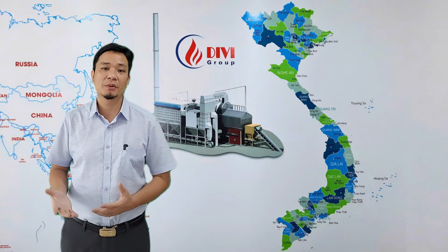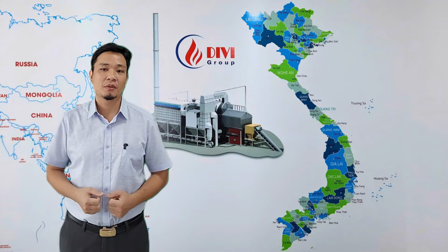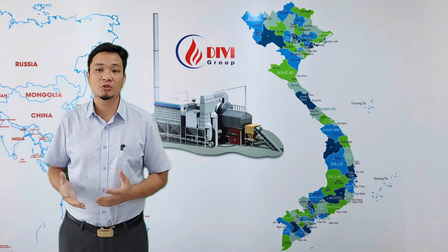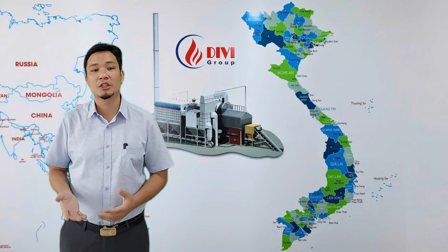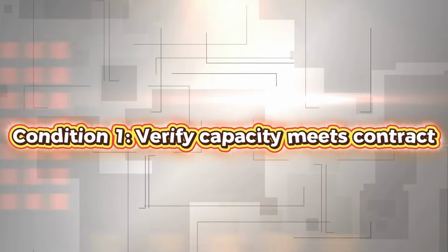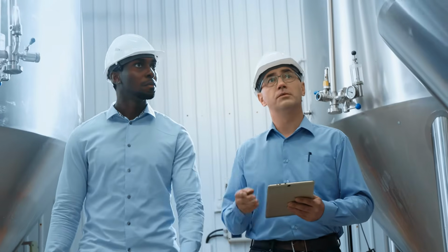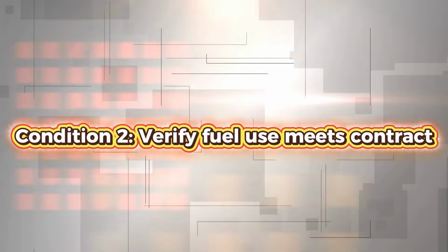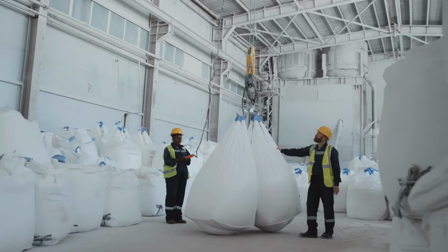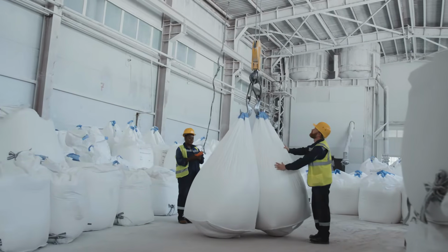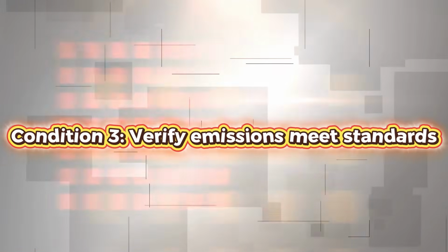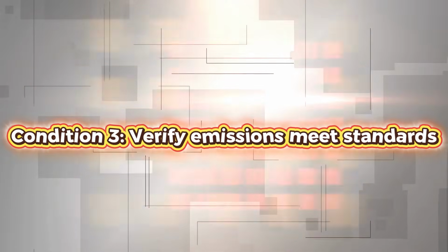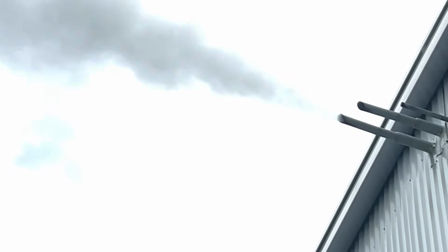So why does this misleading explanation exist? When accepting a boiler, customers usually require 3 basic conditions. Condition 1, prove the capacity matches the contract. Measure steam flow per hour with a flow meter. Condition 2, prove fuel consumption matches the contract. Weigh the fuel to measure actual consumption. Condition 3, prove that boiler emissions meet environmental standards, verified by an independent third party.